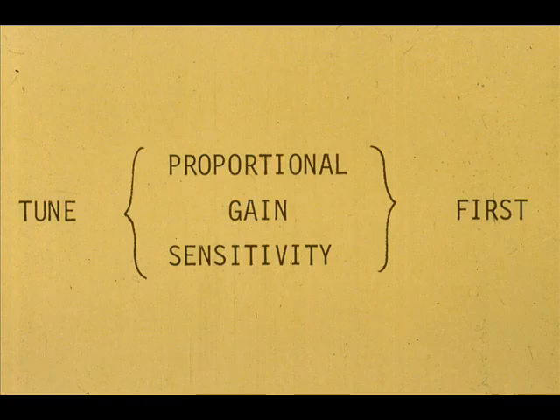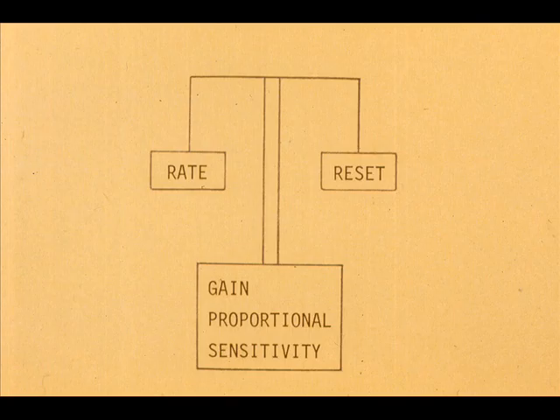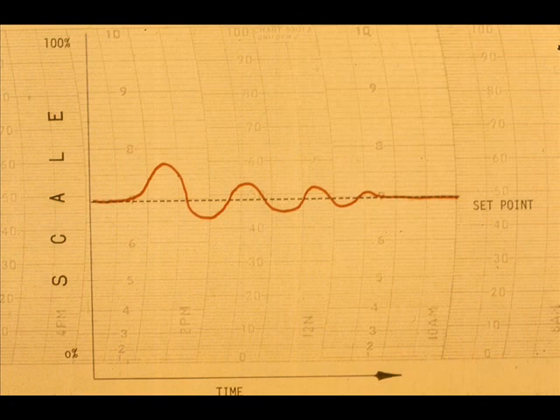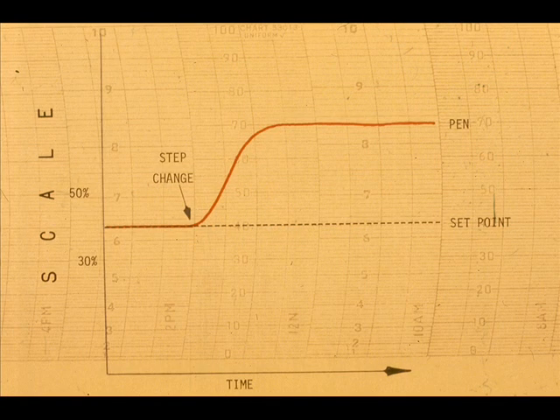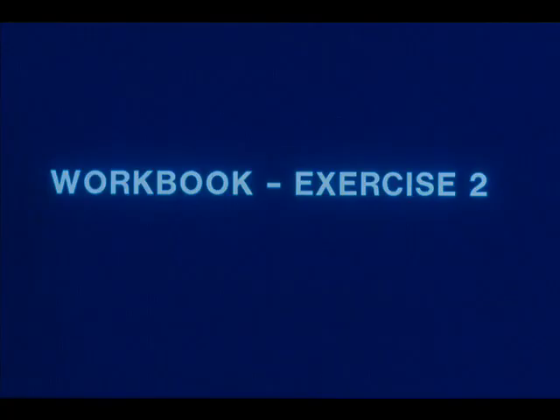Any tuning method must first work with the proportional response, because both reset and rate get their signals from the proportional response. Neither stands alone. When tuning, the reset and or rate are eliminated as much as possible, while the proportional response is first adjusted. We will study methods by which we make the process cycle and methods by which we make a small step change in the process and make a reaction curve. Now work exercise two in your workbook.